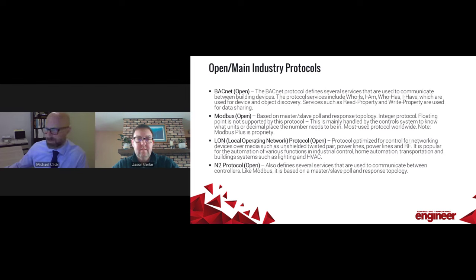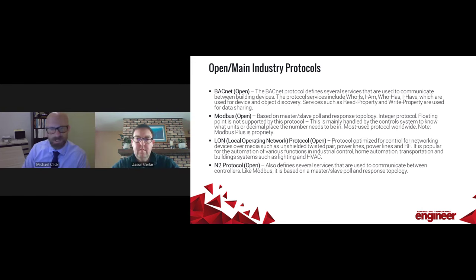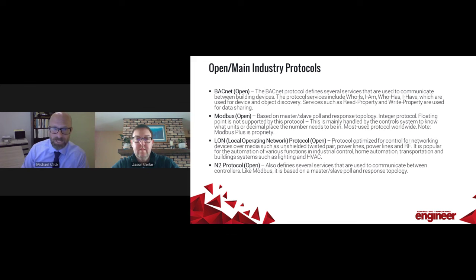There are really four main open protocols used in the industry. BACnet, by far the most utilized. Modbus is also used in combination with BACnet or others to incorporate electrical equipment, found all across campuses. LON is very similar to BACnet and also considered open, but we don't see it quite as much. Then there's the N2 protocol designed by a controls vendor. Both N2 protocol and Modbus have proprietary software versions — if you specify Modbus or N2, make sure you specify the open version.